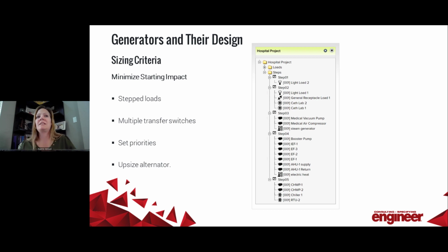One of the best ways to size your generator system is to use the load sizing software that's available. All of the major generator manufacturers have programs you can use. They're typically free and available at your disposal. These software packages have built-in load types which we've discussed. They've got inductive loads, nonlinear loads, medical imaging loads, the list goes on. And the good software systems also allow you to input various parameters, such as the voltage and frequency drop limitations that we discussed. Once you've defined the load types, you can simulate what will happen and the impact it will have on the size of the generator as you begin to bring those loads online.